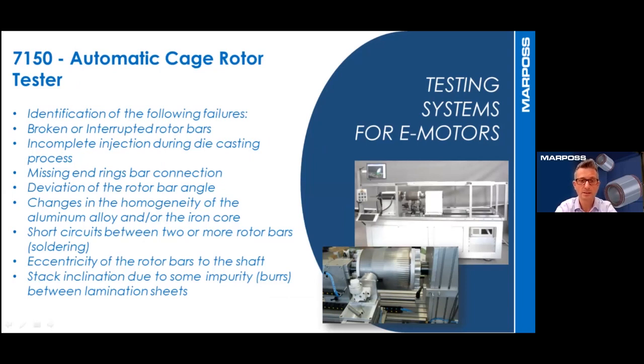The rotor under test is placed in rotation in the machine, and a special probe designed by EDC generates a magnetic field and acquires the signal induced by the bars when they cross the magnetic field. The acquired signal is processed by a special algorithm that identifies all kinds of defects, such as broken bar, porosity, holes, eccentricity of the bar, and so on.